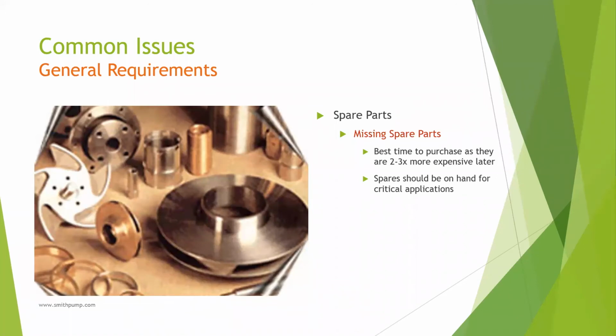So forgetting to add spare parts can be very costly later. During manufacturing, the machine is set up to cut wear rings, the impeller, the shaft, and the bearings. So asking the facility to generate a few spare items while manufacturing the pump is the least expensive time to purchase. Purchasing later is more expensive, due to finding the original blueprint, material sourcing, the machine setup time, and extra shipping costs.